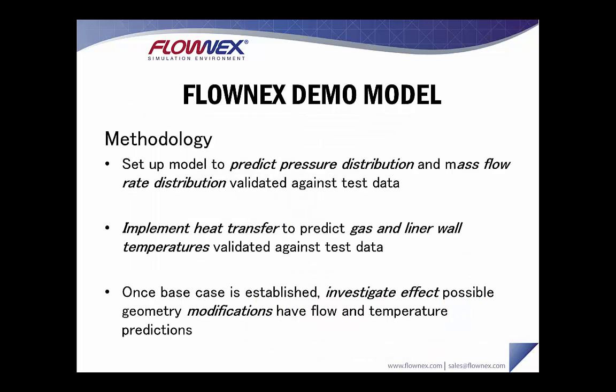The methodology for setting up a Flownex model is to first predict pressure distribution and mass flow rate distribution and validate that against test data. Then one would implement heat transfer to that cold flow model to predict gas and liner wall temperatures, and again validate those results against test or CFD data. Once the base case is established, the effects of possible geometry modifications can be investigated to see how they affect both flow and temperature.